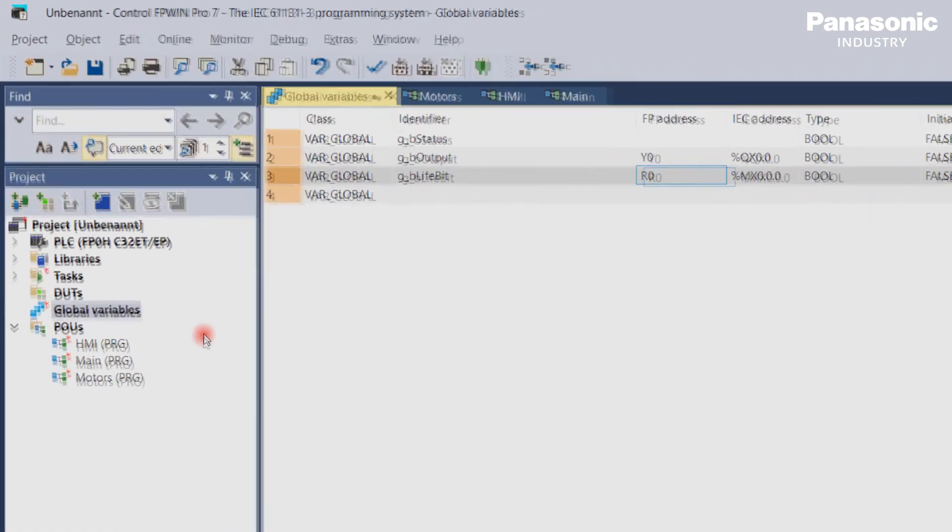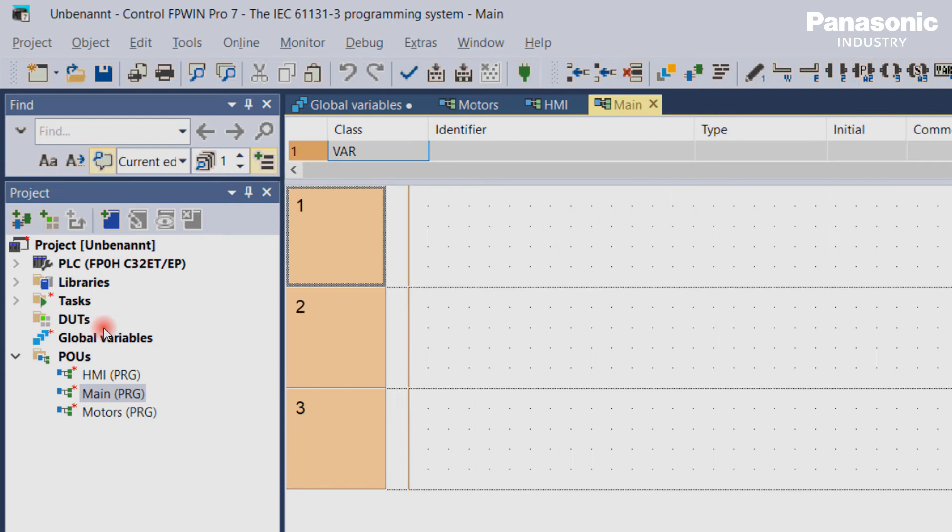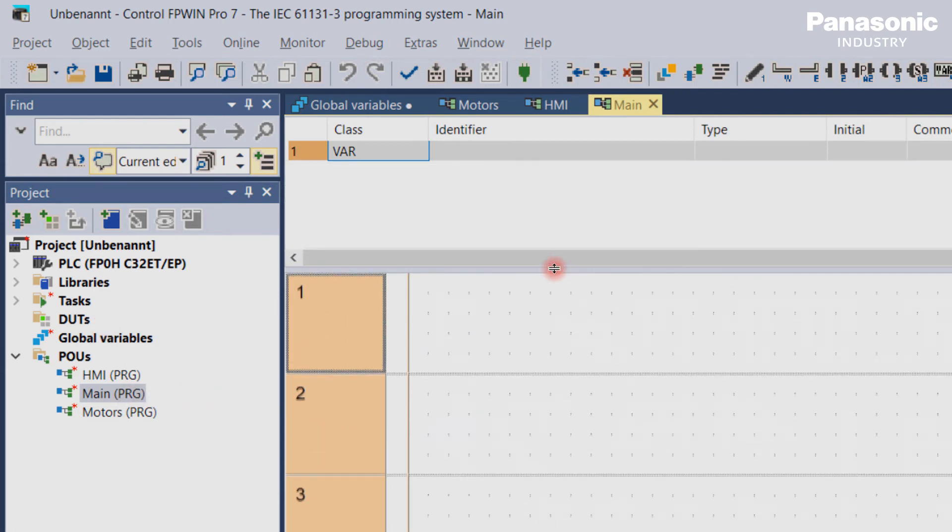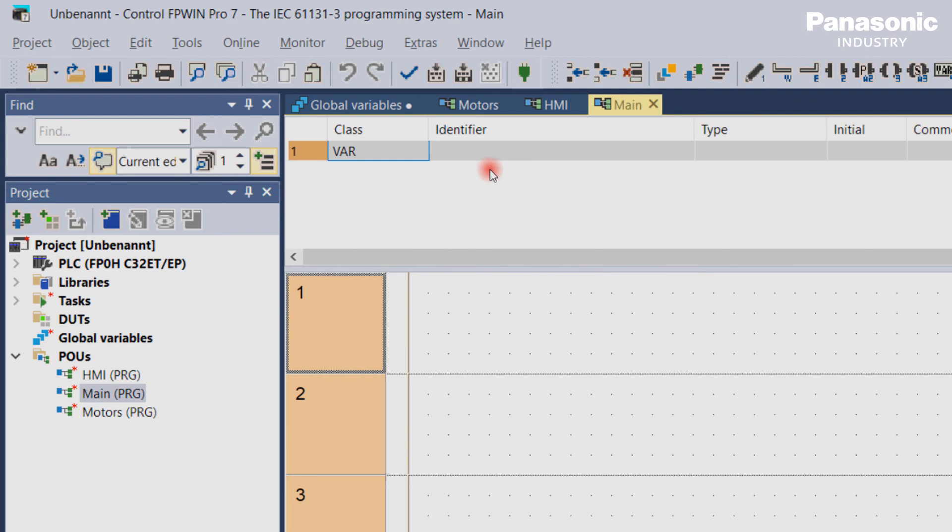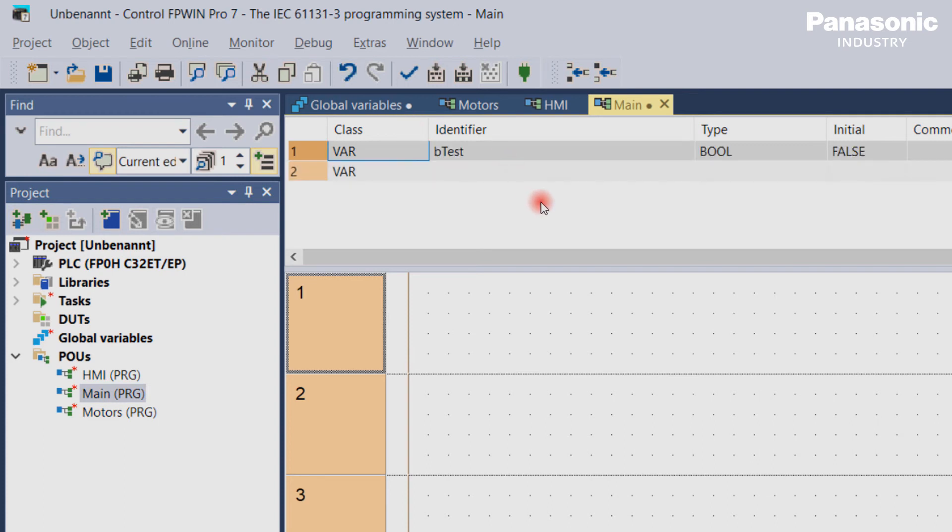Let's make it concrete. We open the existing main program. Inside this program, we define now the local variable BTest. This local variable is only valid inside the main program and cannot be used in HMI or motors program. The keyword here is encapsulation to make your PLC project structured and easier to read.